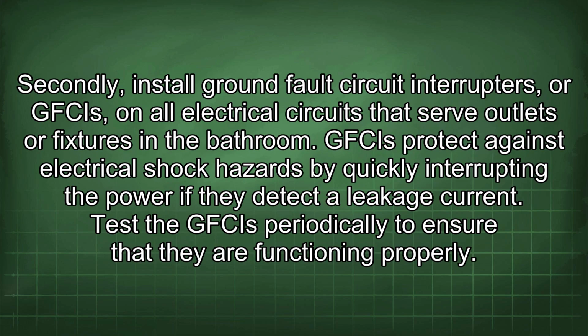Secondly, install ground fault circuit interrupters, or GFCIs, on all electrical circuits that serve outlets or fixtures in the bathroom. GFCIs protect against electrical shock hazards by quickly interrupting the power if they detect a leakage current. Test the GFCIs periodically to ensure that they are functioning properly.